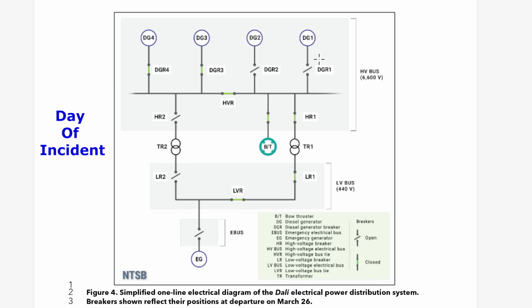And so what happens is these generators here give us the 6600 volts on the high voltage bus. Then it steps down through TR1, which is a 15:1 ratio step-down transformer to get us to 440. So see, if you divide 440 into 6600, you get 15. So the windings here are set at a 15:1 ratio to drop it down to 440 volts. But this guy right here tripped. LR1 tripped, and they didn't know why at the time. When this happened, this took out here the 3 steering gear pumps. So there's the first part of your problem with not being able to steer.